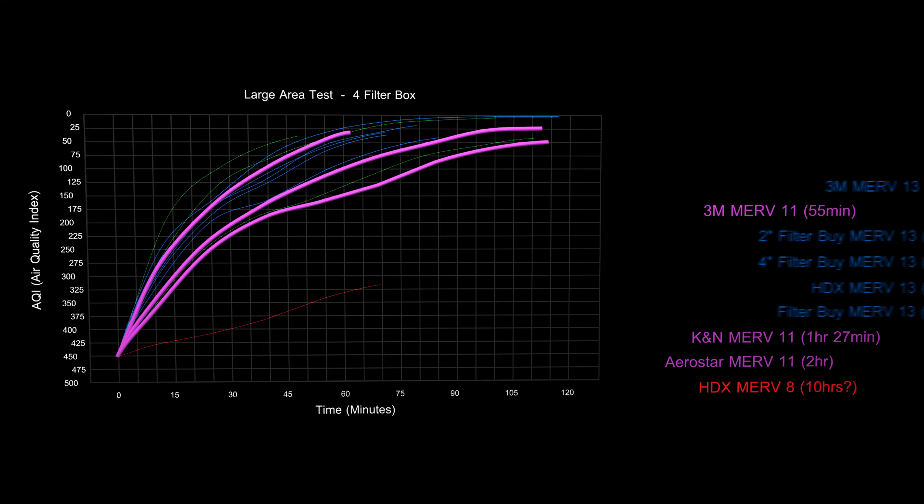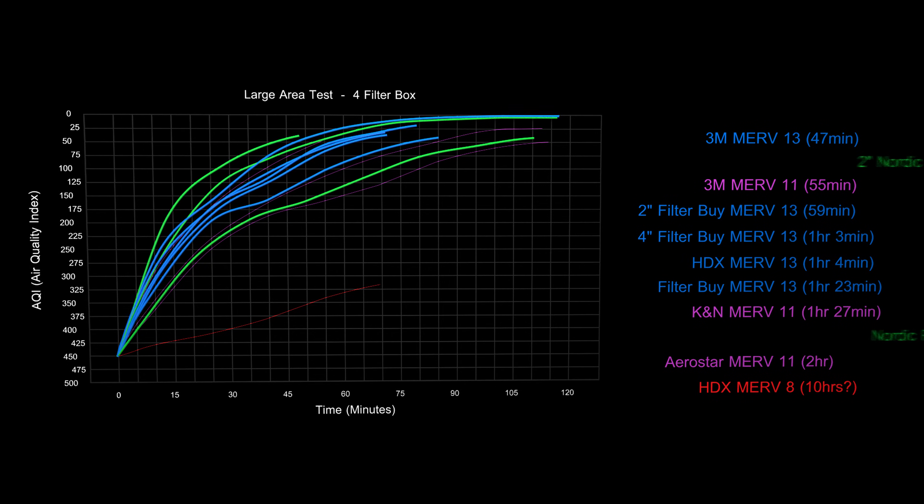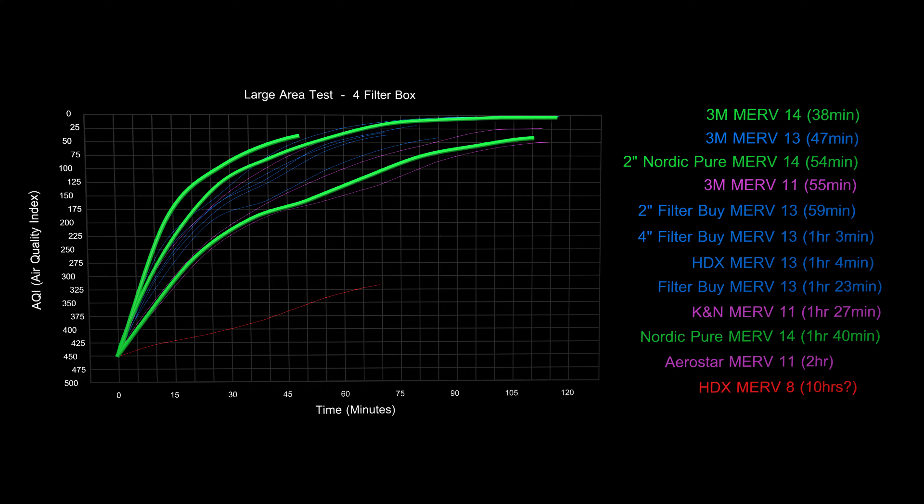At the MERV 13 level, the 3M filter topped the chart at 47 minutes, followed by the 2-inch and 4-inch Filter Buy, then the 1-inch HDX filter, and about 20 minutes later the 1-inch Filter Buy. For the MERV 14 level, the 3M filter produced the best results seen in this test, taking only 38 minutes to clean the air in this large space. It was followed by the 2-inch Nordic Pure at 54 minutes, and the 1-inch Nordic Pure finishing 45 minutes after that.